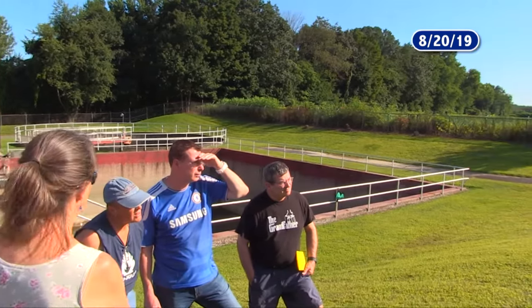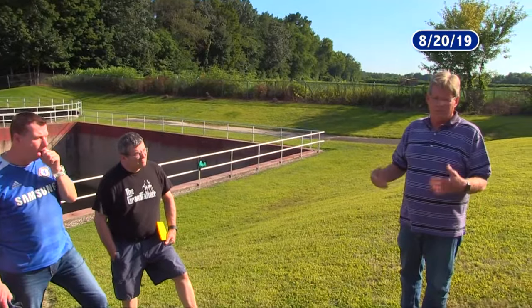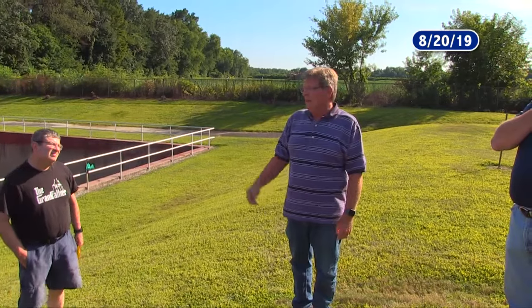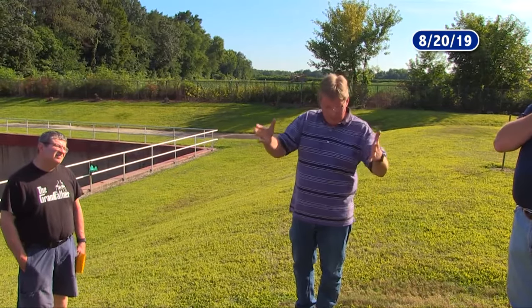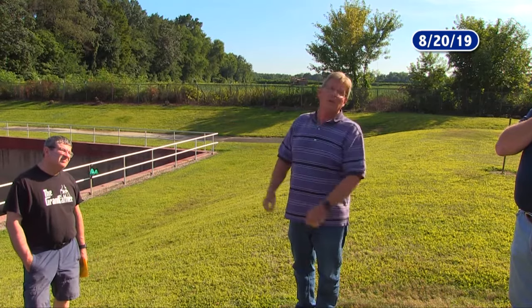Comes from what? From the town. From the users and the restaurants. And we've tried to address that numerous times and we're getting nowhere fast with it. This last month, the month of August, we started cycling this air on and off an hour at a time, not only to save electricity, but I'm trying to experiment with nitrification, denitrification, and it's working out really well.